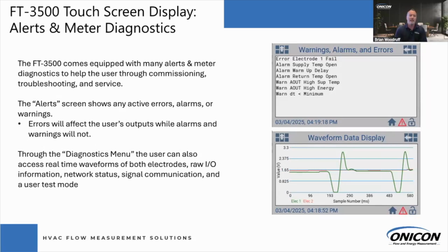Also, we have the alerts and meter diagnostics, which is great because you're able to see all the errors, alarms, and warnings that might be keeping your flow meter from operating as advertised. So again, as I mentioned, if you called tech support previously, you would just have an alarm state. So it triggers at your BAS and you're like, my flow meter's not operating. What can I do? Well, from the tech support standpoint, you're having to troubleshoot: is this the BAS side of things? Is this the flow meter? Is it inserted in the pipe?